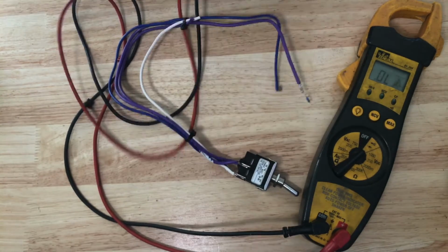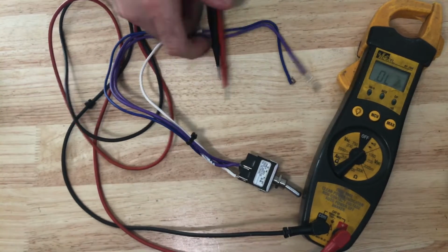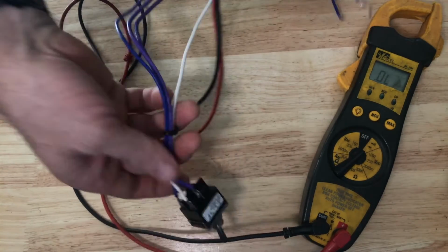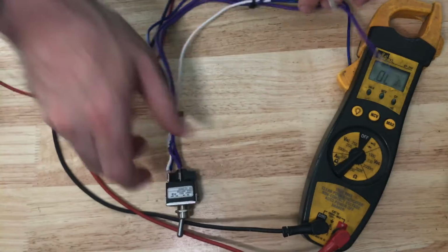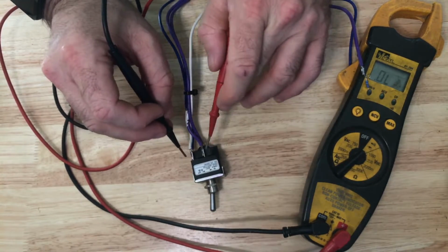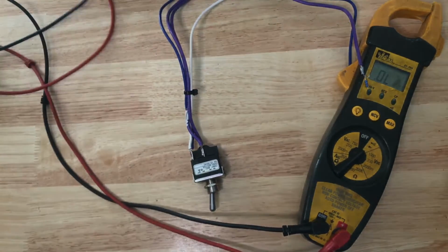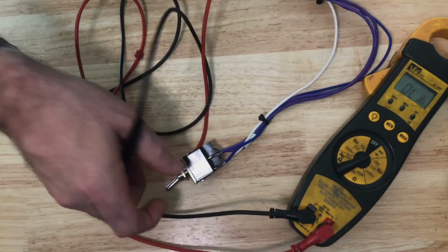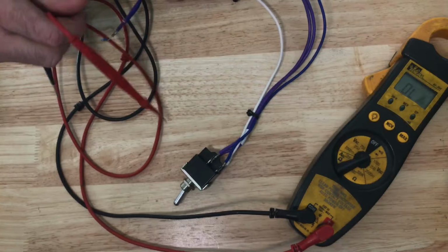I'm not really concerned, as I said, what the actual resistance of that circuit is. I just want to know that there is one present. And I could also do that just down the length of a wire. If I was not sure if this switch was working, if I tested it here at the switch contacts and everything seemed to be fine, then I would think, well, perhaps my fault is in the wire itself.